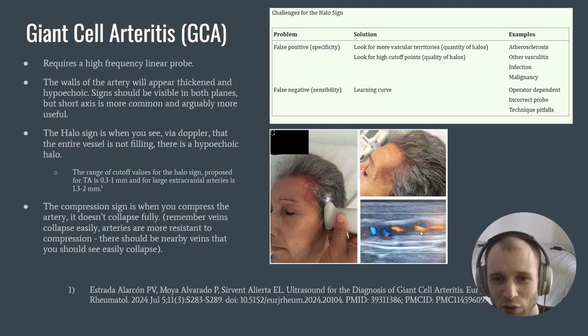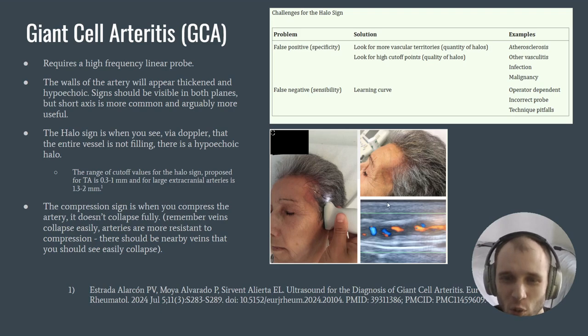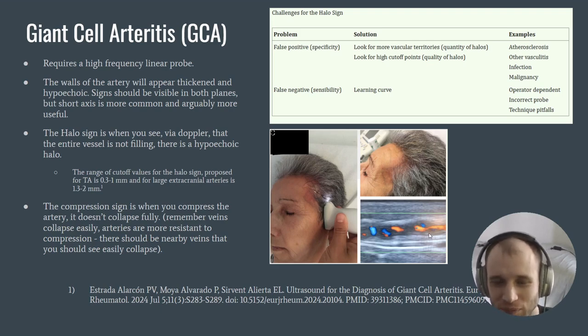Remember that the flow has to be coming towards or away from the transducer. We can't see here because of the cropping, but this person probably has the little box tilted so that there can be flow towards or away from the transducer. Because if there's no flow towards or away from the transducer, color Doppler and power Doppler won't do anything for you. Right, so either heel-toe the transducer, or in the case if you're looking at short axis, tilt the transducer, make sure there's an angle to it so that the flow can come towards or away from the transducer. Right, and if you're following that, then you should see some pulses.